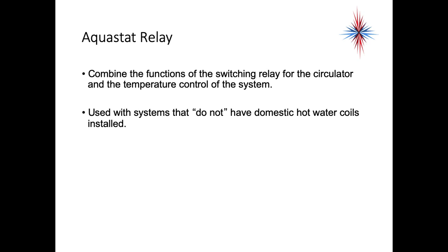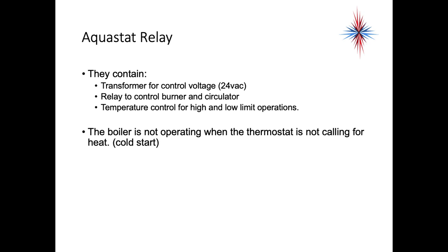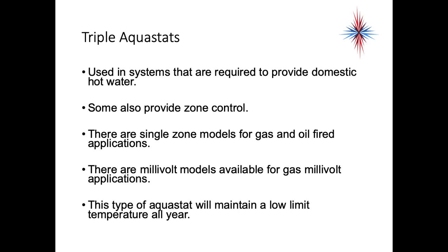Aquastat relays are used in systems that do not have domestic hot water coils installed — in other words, we do not need to maintain a higher boiler water temperature. They contain the transformer for control voltage, a relay to control the burner and circulator, and temperature control for high and low limit operations. The boiler is not operating when the thermostat is not calling for heat — it's a cold start boiler, meaning it will get cold before it starts up.